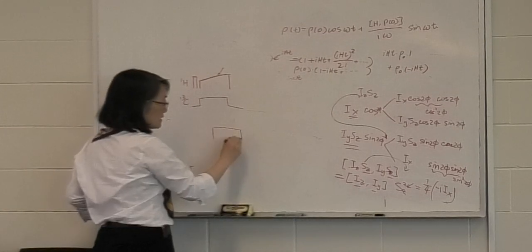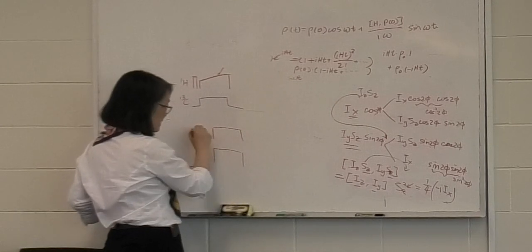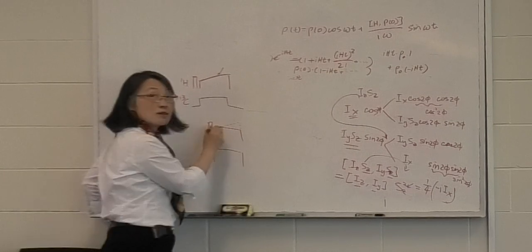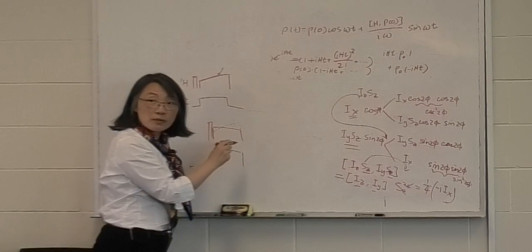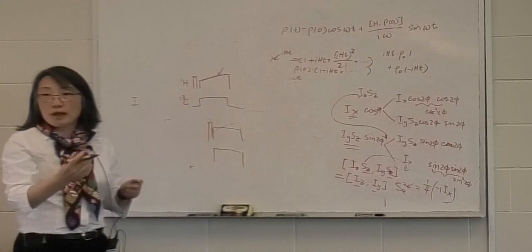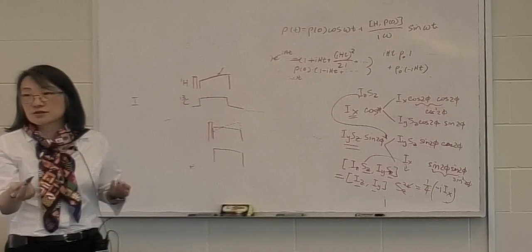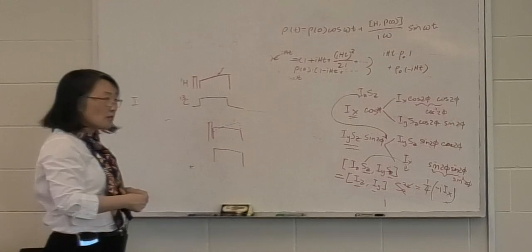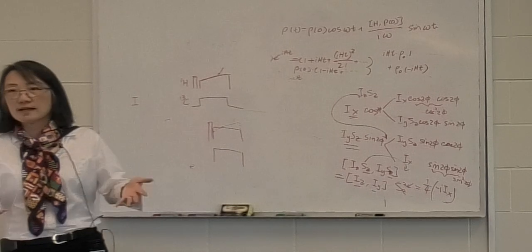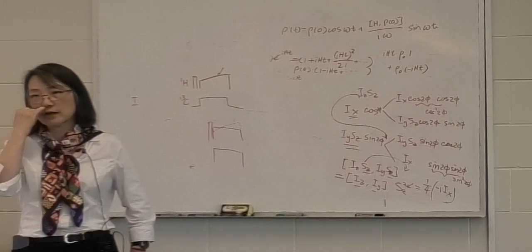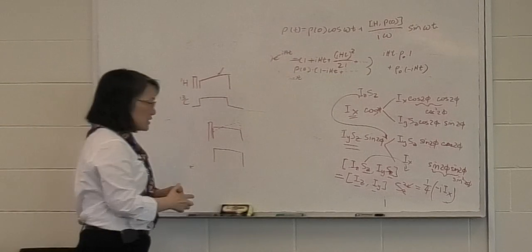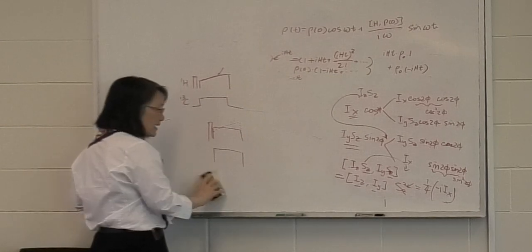So if you think that the perfect CP amplitude should be something like this, you can say I'm going to do a ramp where the middle of my ramp is where it should be perfect. But if my amplifier power level drifted, I shift to a different part of the ramp and I'm still matching the Hartmann-Hahn condition. So that's the purpose of doing it. Otherwise, when you're truly off, you just don't get very good CP. You still get it somewhat. It's not like it fails completely, especially under magic angle spinning conditions. Well, actually, let's just say under static conditions.